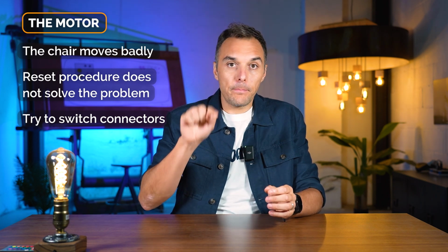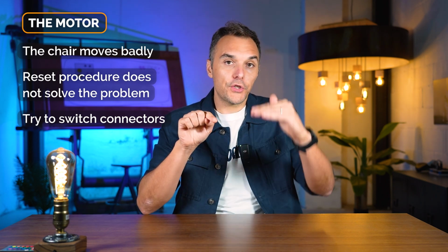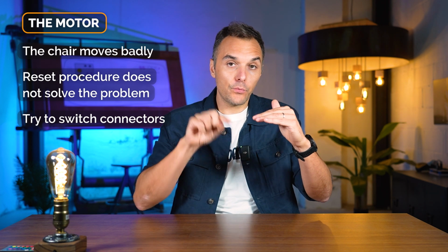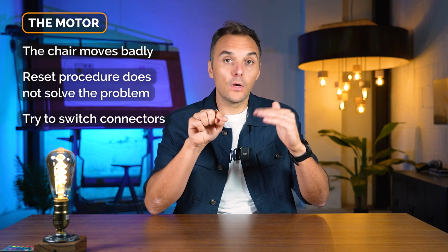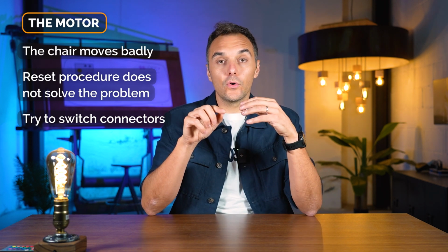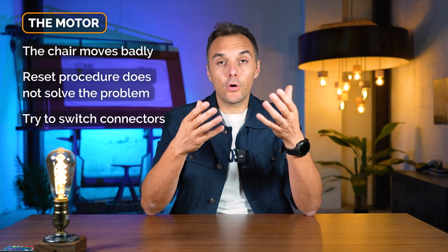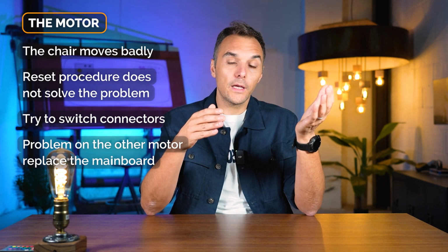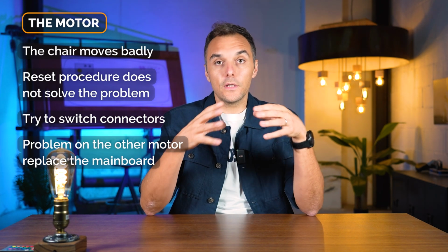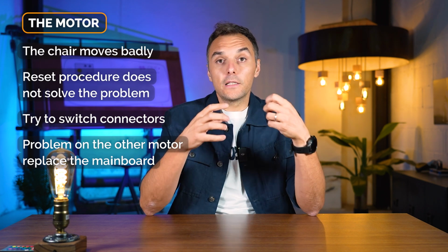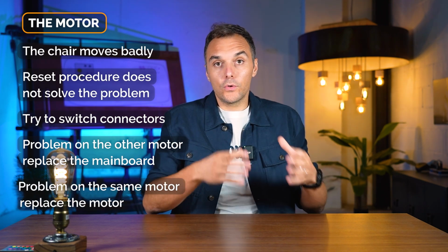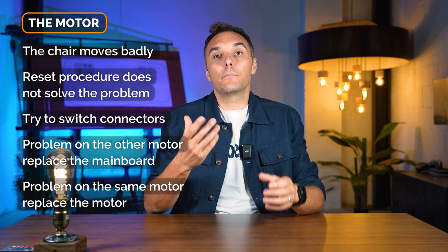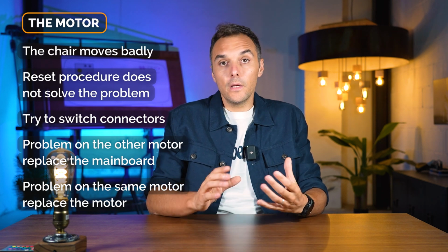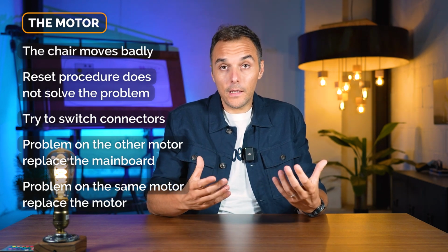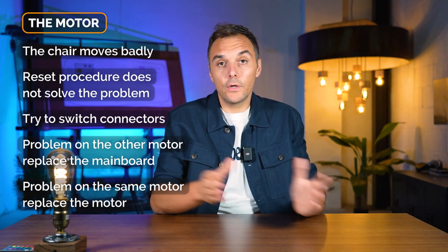Normally when we press the upper button, we move the motor of the chair, but if we switch at the base, when we press the upper button we are now moving the backrest. So we can see immediately if the problem transfers to the other motor. If so, it's the main board that has the problem. If the problem remains on the same motor, the same movement, then the problem is in the motor itself. This way we can easily identify where the problem is, the motor or the main board.